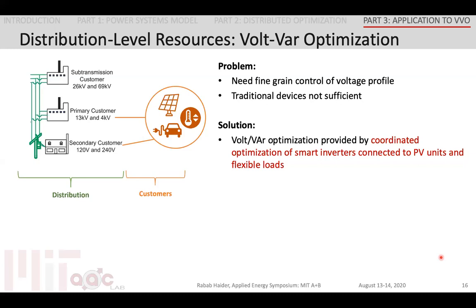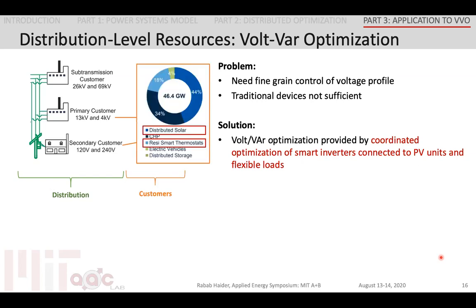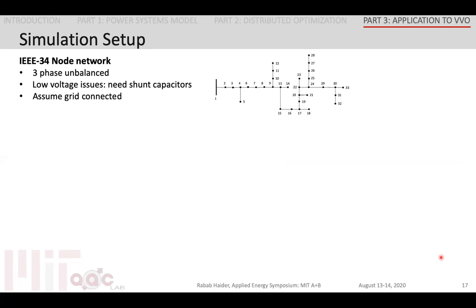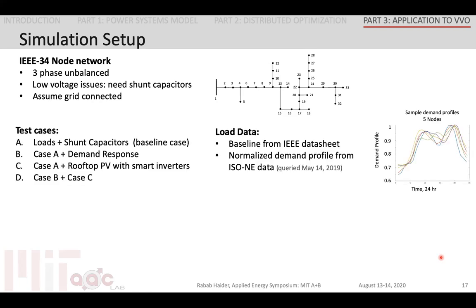With these two tools in our toolbox, we can now solve the Volt-VAR optimization problem by looking at the coordination of PV smart inverters and flexible loads, including smart thermostats and distributed solar. We carried out VVO on the IEEE 34 node network, which has low voltage issues even though there are shunt capacitors in the network. We then run different test cases with varying penetration of DERs. Case B looks at the baseline with demand response. Case C looks at the baseline with additional PV and smart inverters with variable power factor. Case D tests the limits by looking at both of these resources together. We use load data from New England to generate demand profiles for each node in the network.